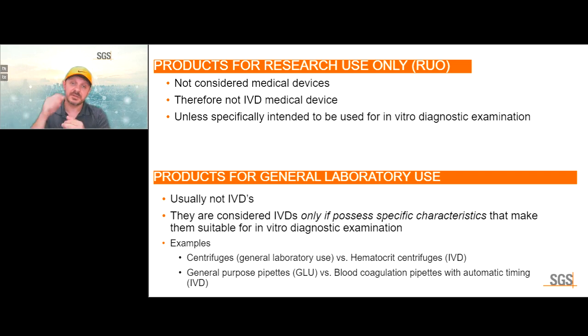For research use only devices, if desired by the manufacturer, we can provide ISO 9001 certification. Products for general laboratory use are typically not IVDs — they are only considered IVDs if they possess specific characteristics that make them suitable for IVD examinations. For example, general centrifuges are general lab use, but a hematocrit centrifuge is an IVD accessory. General purpose pipettes are not IVDs, but blood coagulation pipettes with automatic timing can be an IVD device.